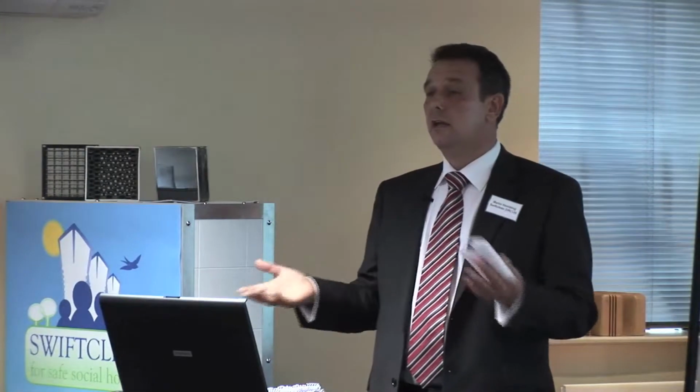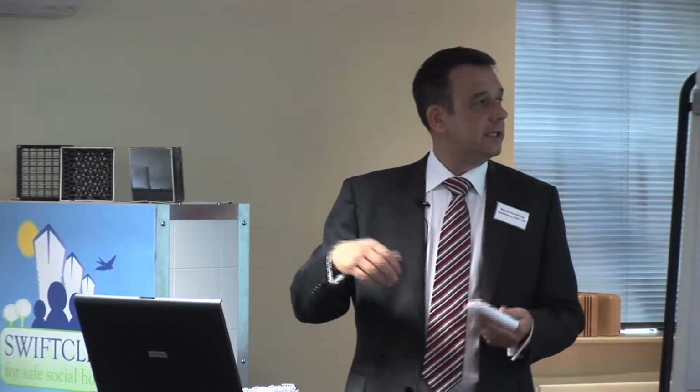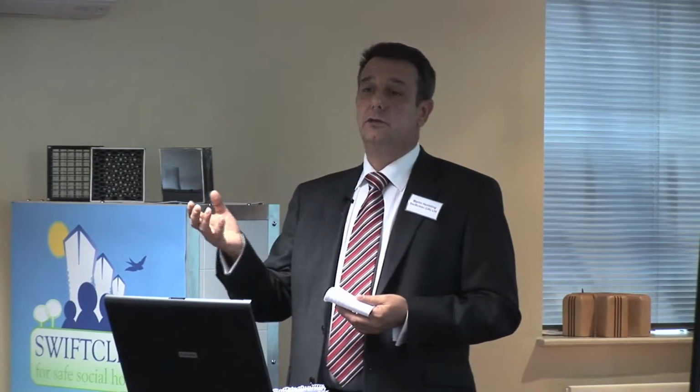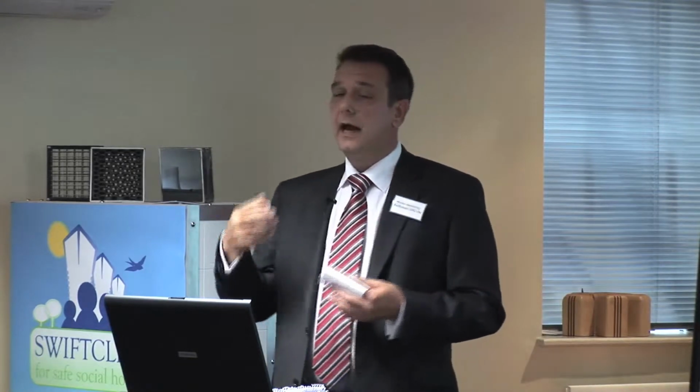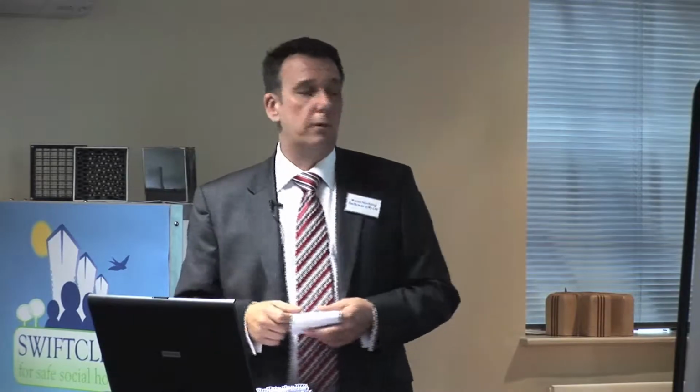Now, regular basis could be every 5 or 10 years. It could be every 1 to 2 years. No one can give you that magic answer because we don't know. So you have to monitor it. And the best way for the companies or the boroughs that are looking after it is to have a regular monitoring scheme, which may be once every 2 years, just to have a look behind the grills. Take some grills out of the wall and have a look, see what's behind there. If it's blocked, there's no airflow, then you've got a problem.